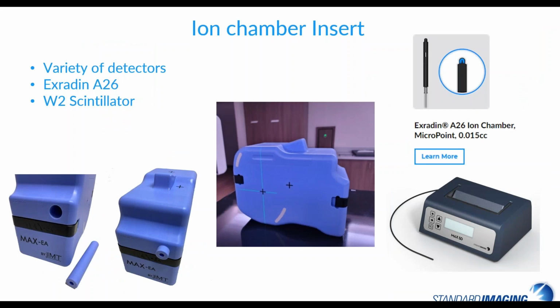For ion chamber, you can use a variety of detectors. You can see there on the bottom left, that's the ion chamber insert. It's basically a sleeve, which is drilled for your specified ion chamber. Of course, we recommend the small volume chambers like the Exradin A26. You can also use the W2 scintillator as well with the Phantom.